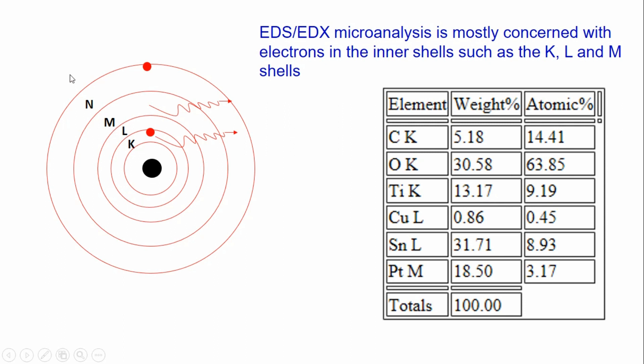When we bombard electrons from the SEM machine on the specimen, it will knock out the innermost electron. When it knocks out that electron, there will be a vacancy, and the other electron living above it will try to fill that vacancy. Because of the difference in energies between these two electrons, energy will be emitted — we call this X-ray, specifically characteristic X-ray, because we want to know the characteristics of the material.